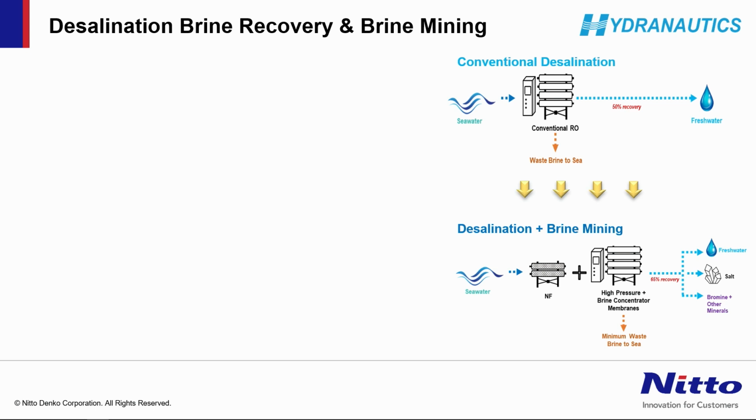And then you also have what we call the reject, and it's also called brine in many cases. If you look at the recovery, it's very limited because of the TDS of the water and the pressure requirement, which all comes from the osmotic limitations of the water that you're dealing with. But you can look at 50% recovery. But now, with the advancements we've been making in the field of membranes, you are able to take the same seawater, have a specialty pretreatment in terms of nanofiltration, followed by what we call, again, specialty membranes.